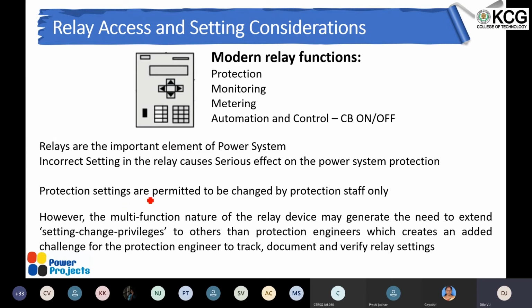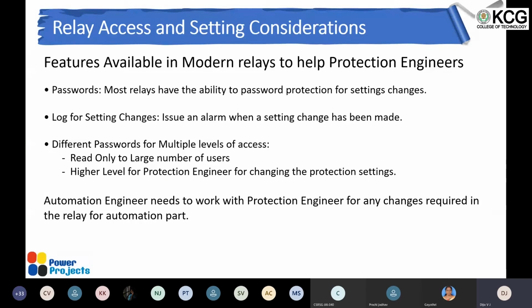So the protection engineer knows the criticality of protection settings. So there is a chance of somebody by mistake changing the setting and then creating an issue in the grid. Some of the feeders can maltrip because of some wrong setting, which the protection engineer is not knowing. So that's the problem. So what are the features available in the modern protection relays to avoid this? So this is considered a cybersecurity issue.